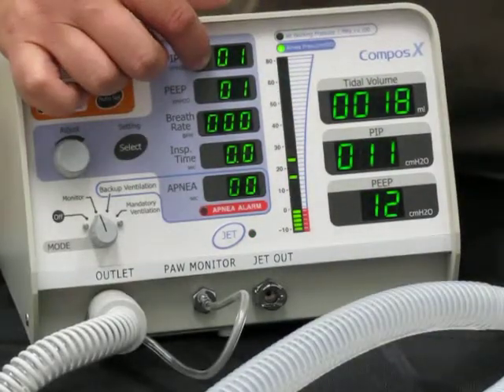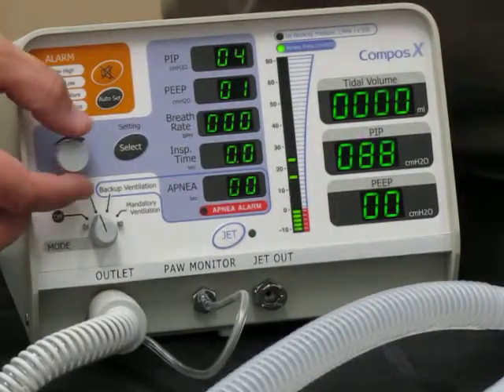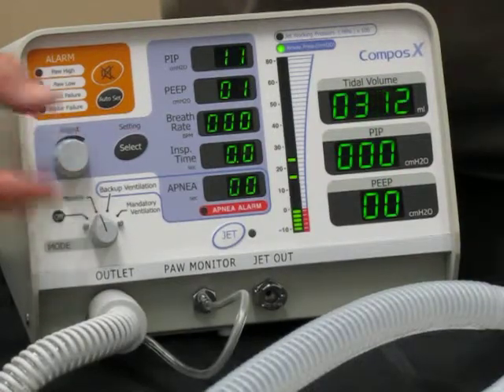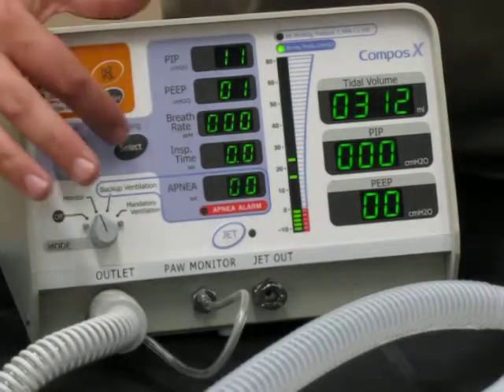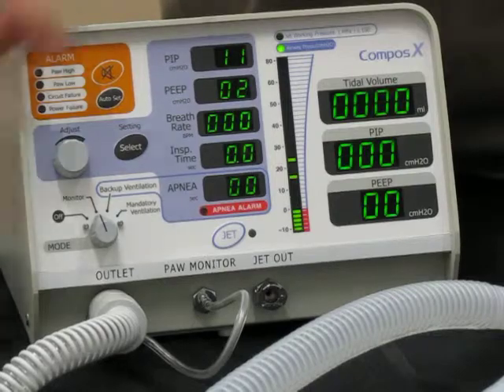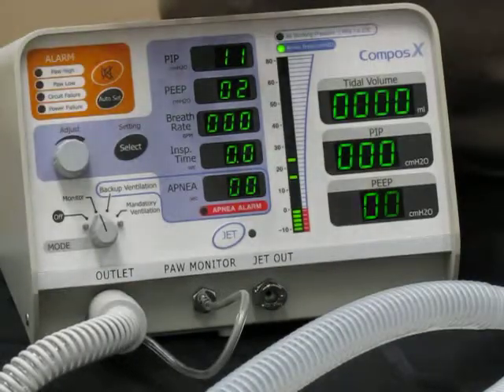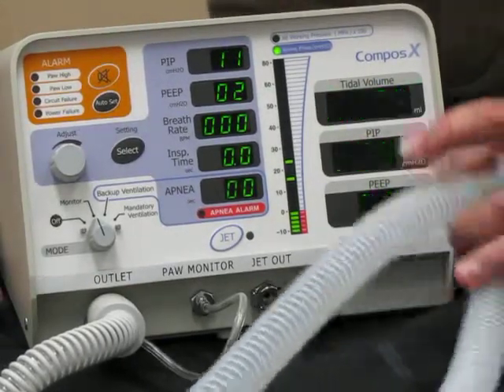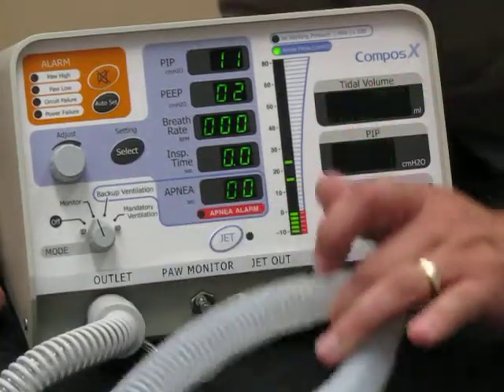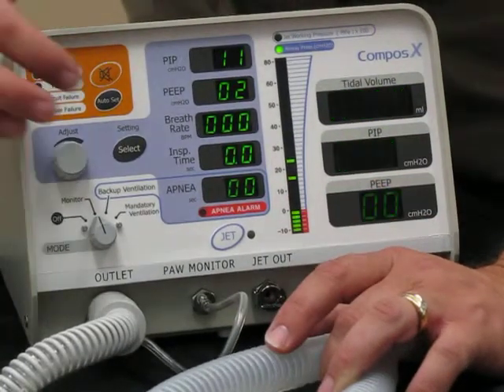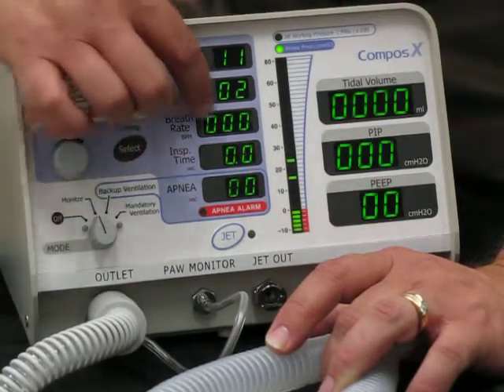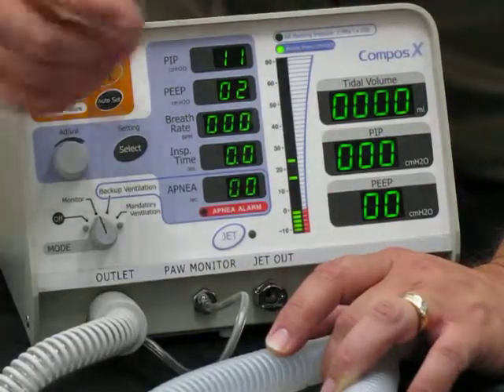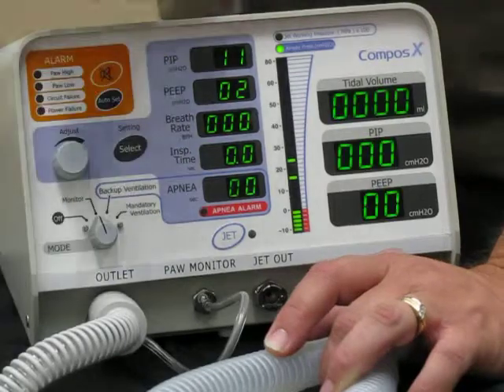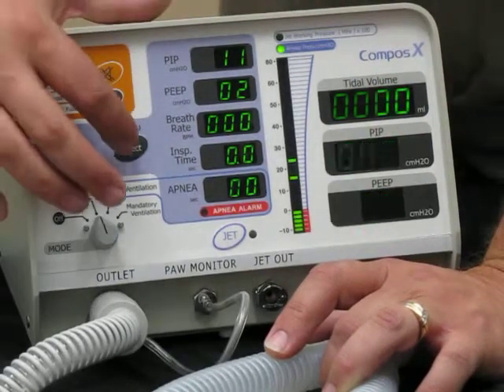You can see you get a couple of 1s up here. We're going to change the top one, which is the inspiratory pressure line, to 11, and I'm going to hit select. At this point it puts it at 2, and the unit is ready to do the calibration. I'm going to occlude the end of the tubes, where I would hook the endotracheal tube up, and hit select. This number will go to 4, and it'll perform its calibration. It takes about a minute, and it's somewhat noisy, so I won't talk during the process.